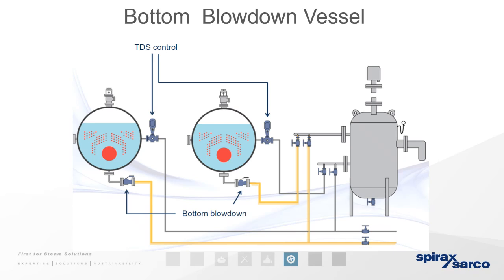So we need to ensure that if we have more than one boiler, we are performing blowdown at timed intervals that allows each discharge to be cooled down significantly before the next one. So what that means is that we need to space them out, so that the blowdown vessel is able to cool the water that's within it, release it to drain before the next boiler starts its blowdown process.